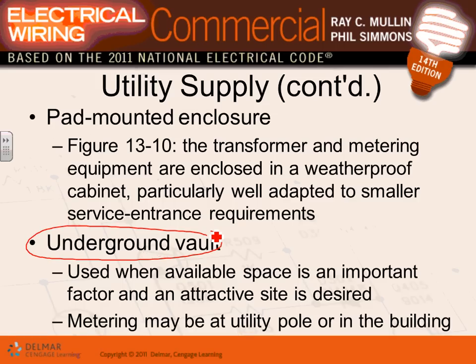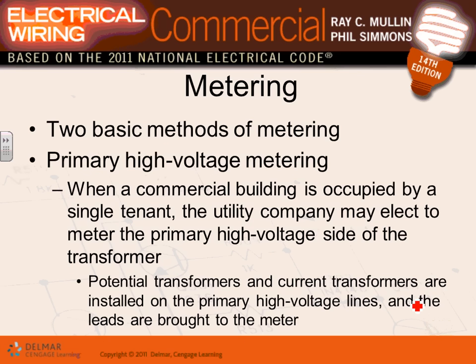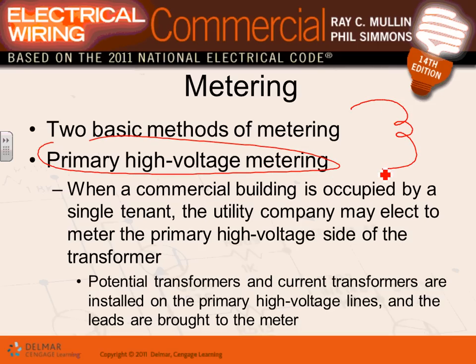Utility pole or in the building. The metering guys, they can either put it on the pole or in the building or the CT cabinet where you put that metering for the utility type. They have two ways of metering so you can pay for it. One is called, guys, primary high voltage. The primary high voltage metering, so here's your transformer.